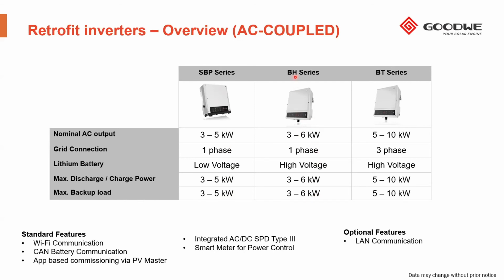The BH series is the AC coupled version of the EH series that you saw on the previous slide. It looks the same because it's basically the same inverter itself. It just doesn't have inputs for the PV array. So that's 3 to 6 kilowatts, single phase, and it's compatible with high voltage batteries from BYD and Pylon Tech. The charge and discharge power is 3 to 6 kilowatts as well, and the backup load is also 3 to 6 kilowatts.